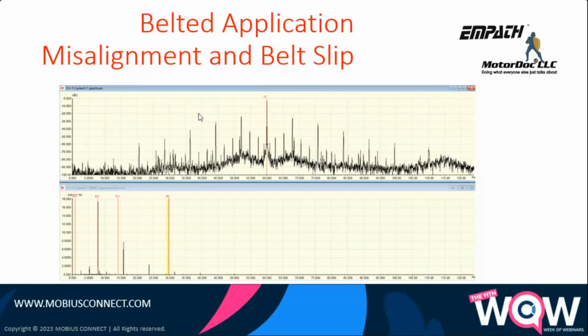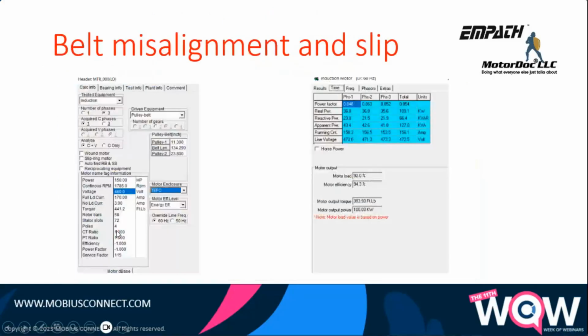Okay, so let's take a look at a belted application with misalignment and belt slip. Again, this is a real application at a facility. So we take a look at it. We do have a resonance, so there's a 2-times belt frequency and a small 3-times. We call these two out. Those we can find as kilowatts. But when I start taking a look at values of this, it'll be significant. So a 150 horsepower machine, 109 kilowatts in, 100 kilowatts out, which gives me a motor efficiency of about 94%. That's actually better than the belt efficiency.